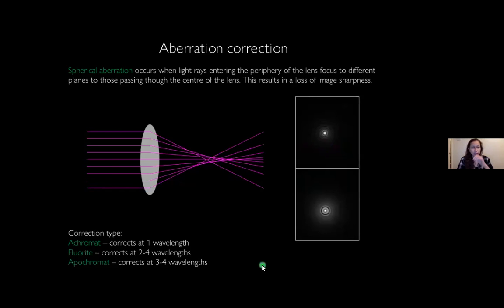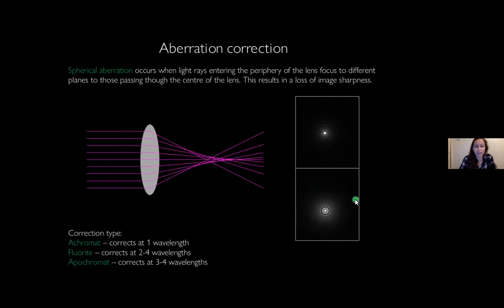The next common aberration is spherical aberration. This is caused by light entering the periphery of the lens being refracted more than light entering the center, meaning the image cannot be brought into a sharp focus — resulting in blurring. The same three lens types can correct for this to some degree: an achromat offers correction at one wavelength, fluorites correct two to four wavelengths, and apochromats three to four.